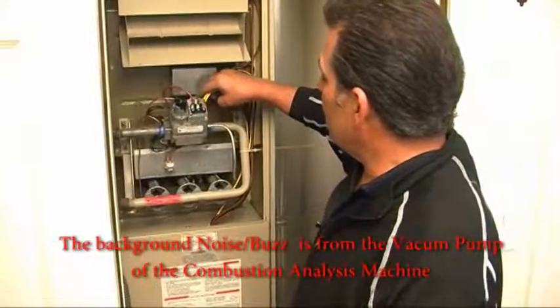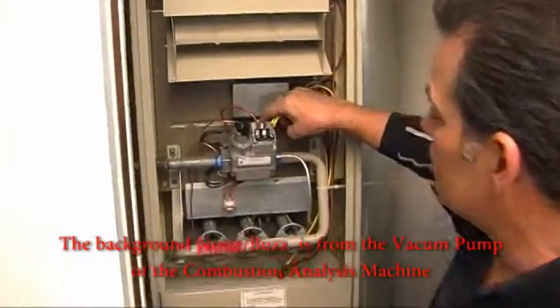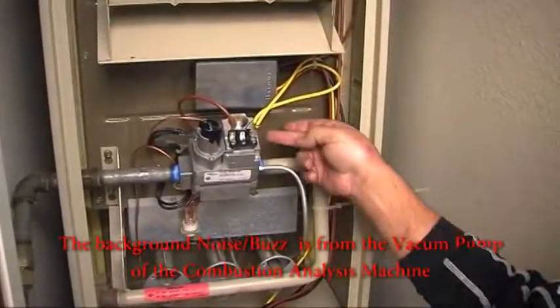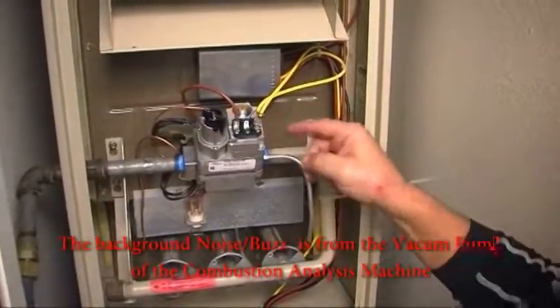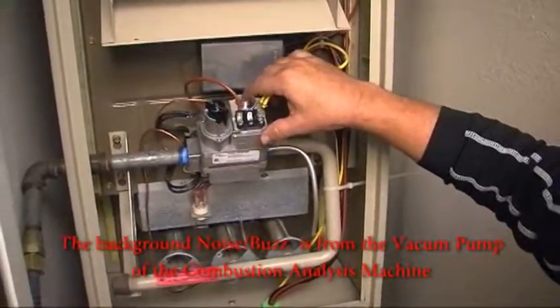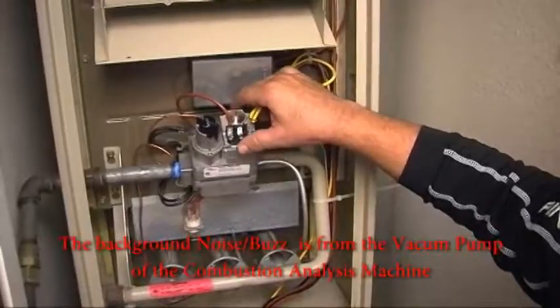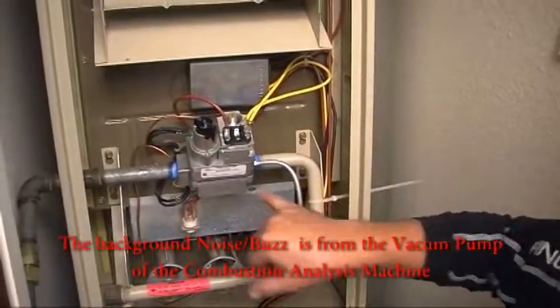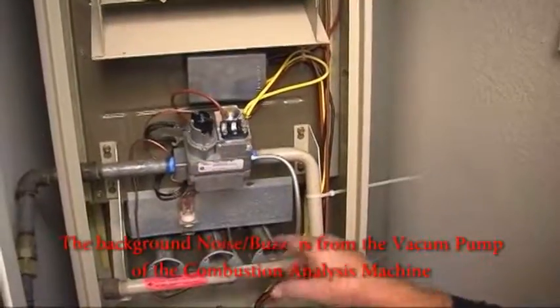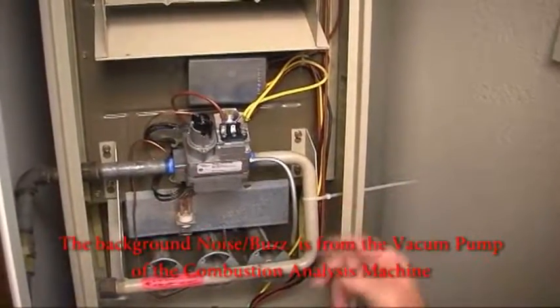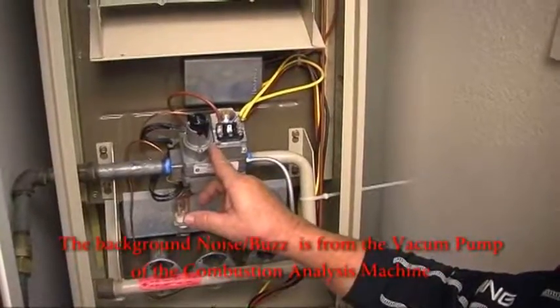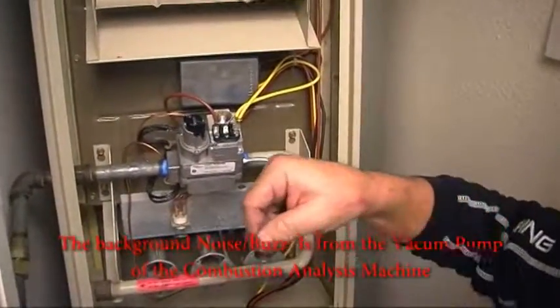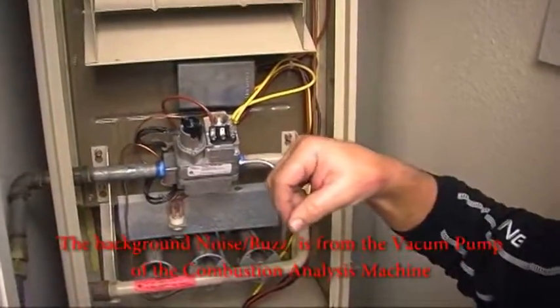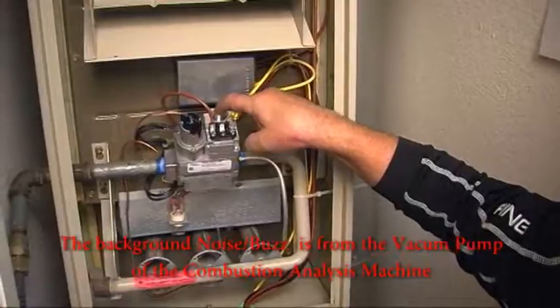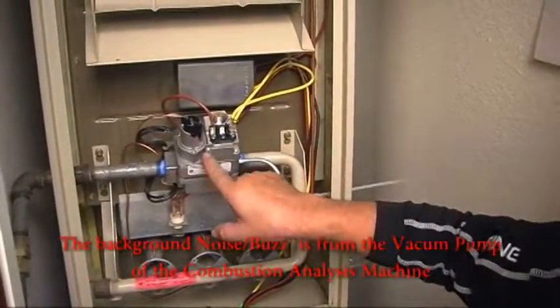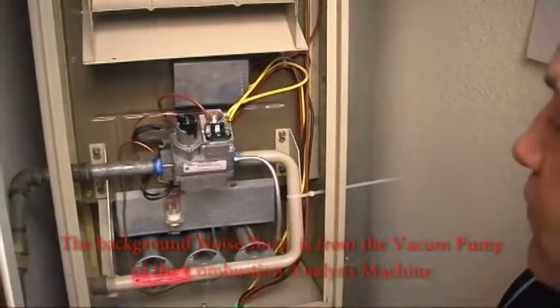While we're here, I wanted to tell you that this screw right here, when you unscrew it, that's where you adjust the gas pressure, in order to do your manifold test port right here. That's where, when you're doing your combustion test, if you need to increase your CO2, you need to turn down on the spring in that area. This screw right here is your pilot adjustment. If your pilot isn't high enough and isn't strong enough onto the thermocouple, you would unscrew this, and then you would put your screwdriver in and turn. Clockwise for more pressure because we have a spring on the regulator of the gas valve, and counterclockwise for more pilot fuel going through the pilot.